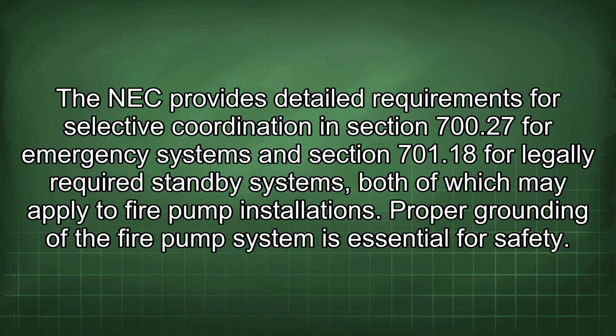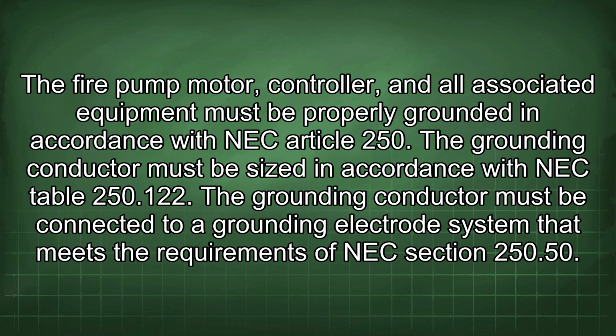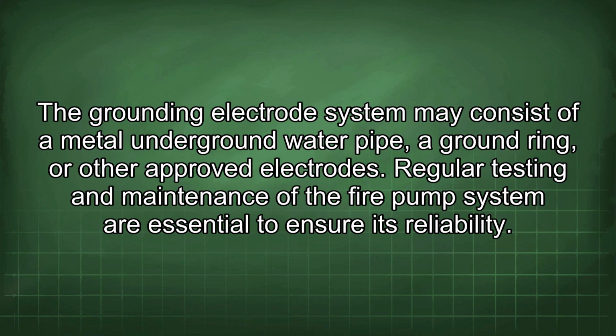Proper grounding of the fire pump system is essential for safety. Fire pump motor, controller, and all associated equipment must be properly grounded in accordance with NEC Article 250. The grounding conductor must be sized in accordance with NEC Table 250.122. The grounding conductor must be connected to a grounding electrode system that meets the requirements of NEC Section 250.50. The grounding electrode system may consist of a metal underground water pipe, a ground ring, or other approved electrodes.